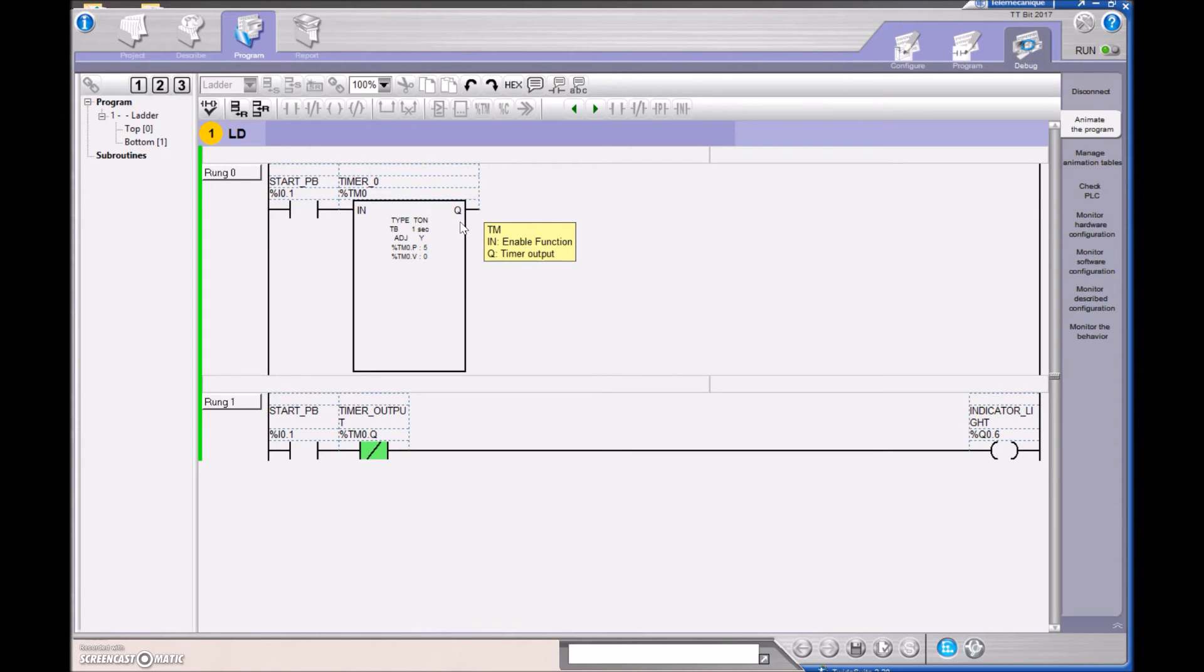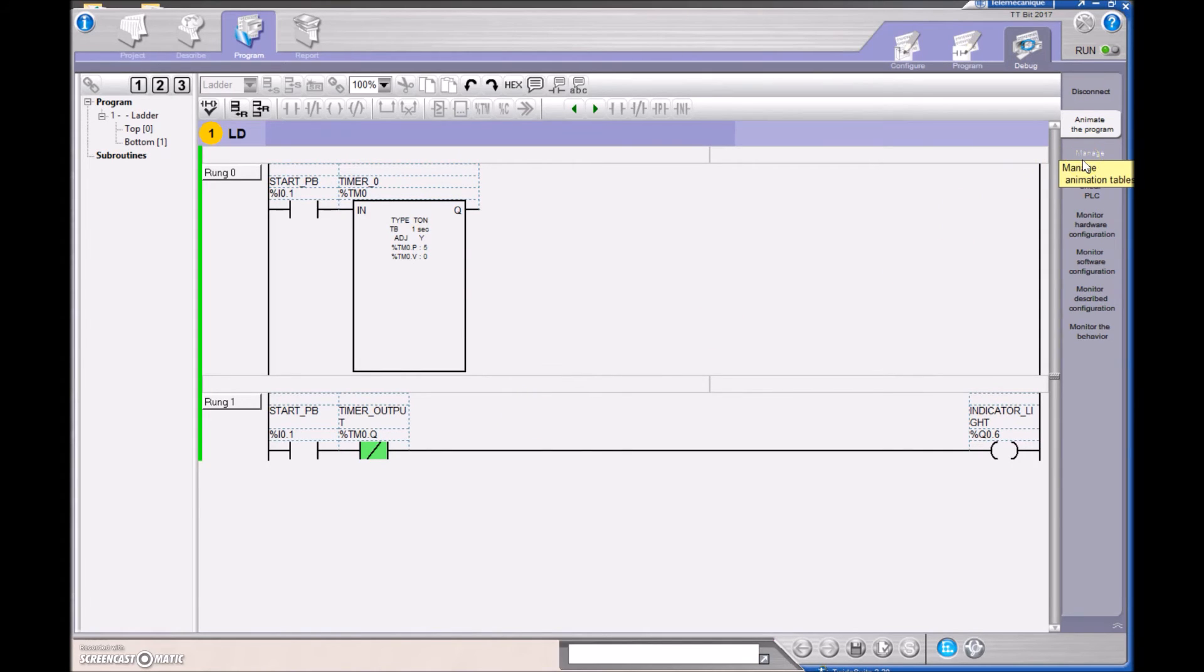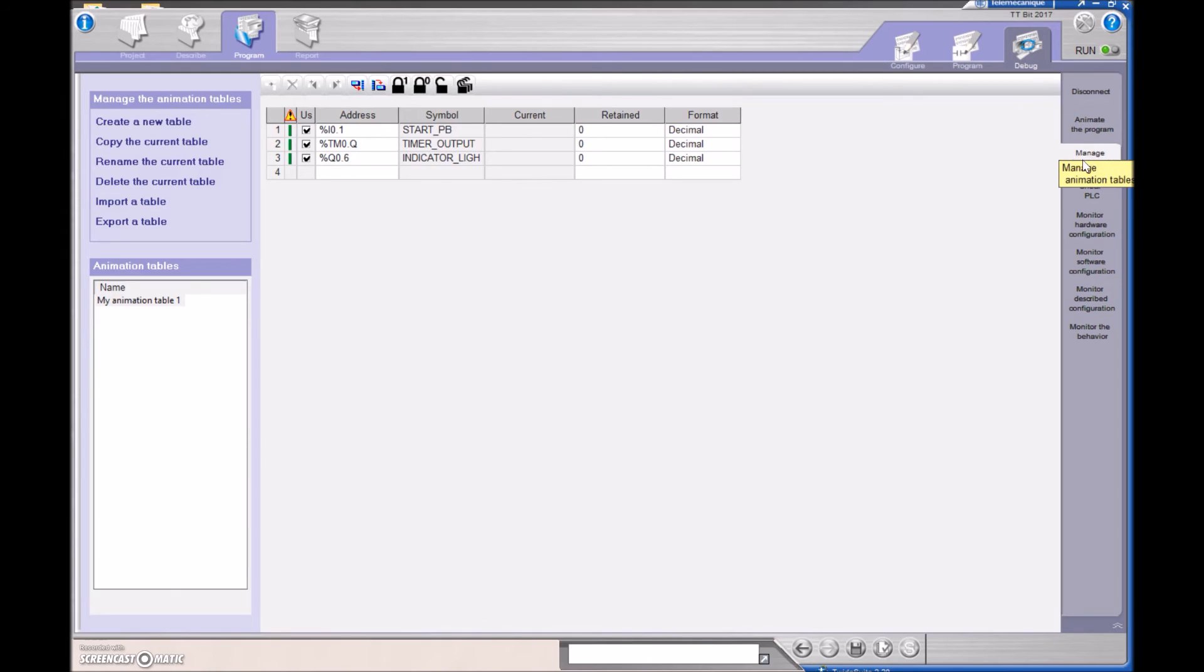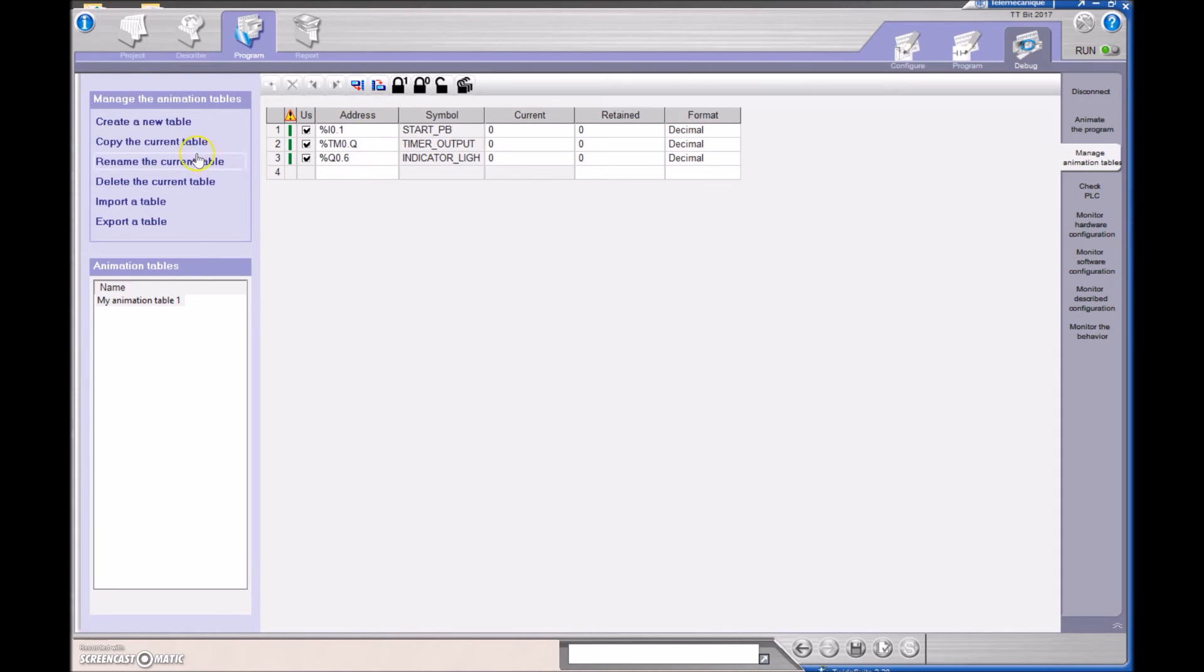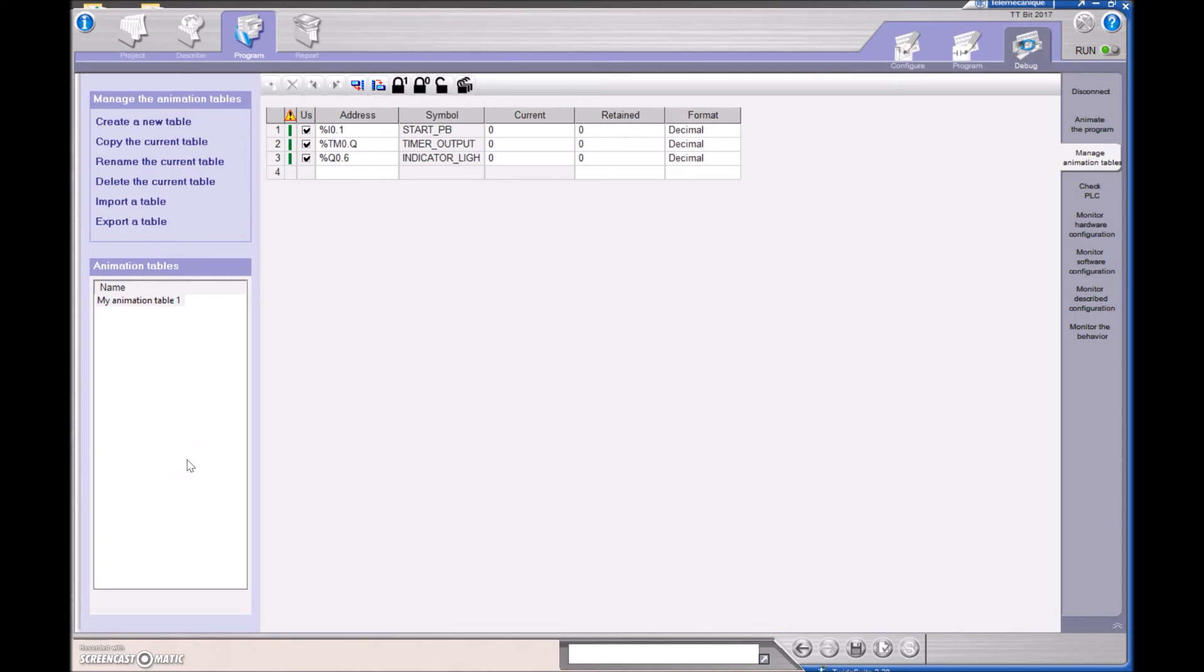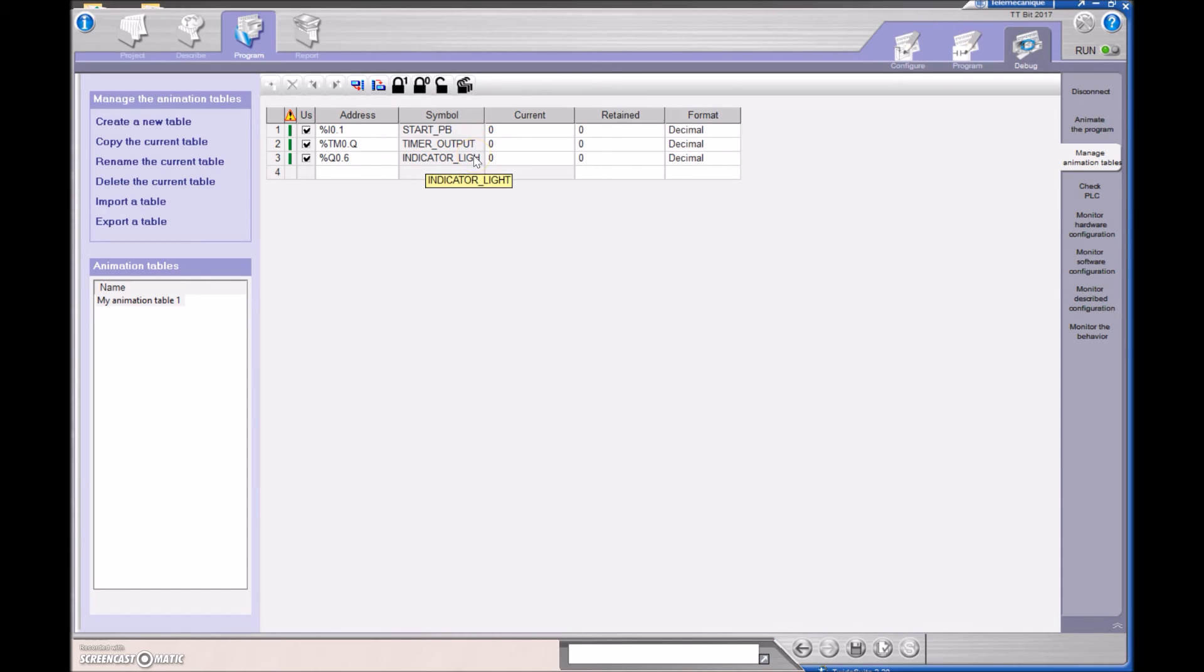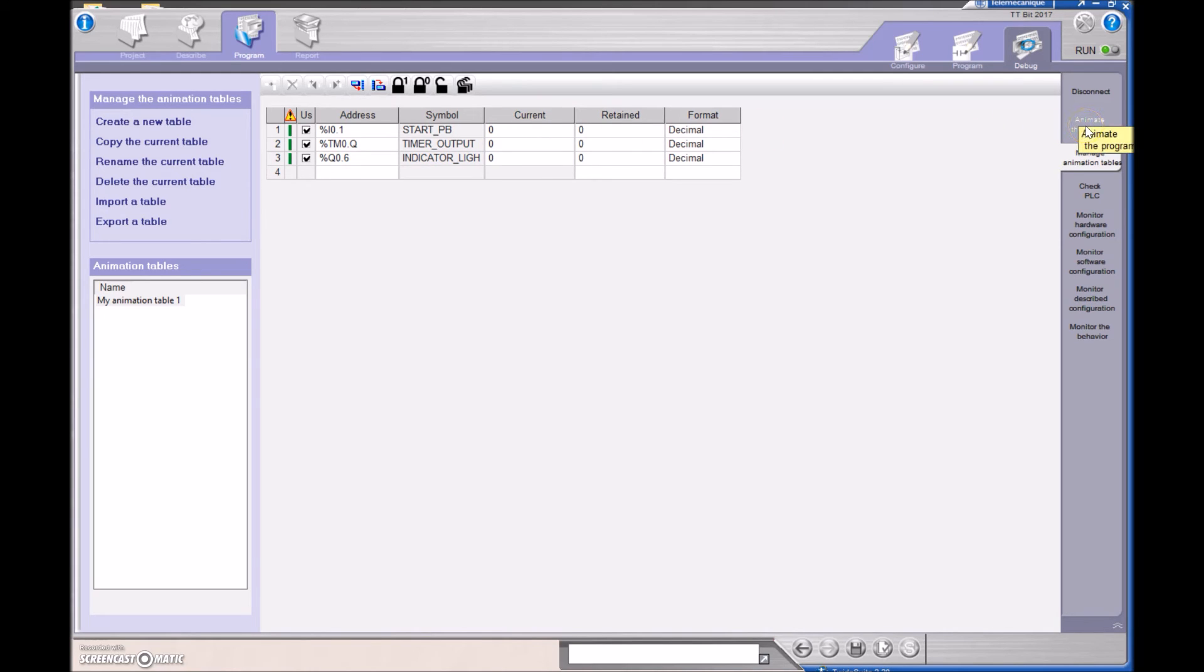The other thing I want to show you in this video was if you want to look at the actual bits, then you can go here to Manage Animation Tables. Now, at this point, I already put in my input, my timer output, and my indicator light, but if this wasn't here, you would just go to create a new table. On the Allen Bradley PLC, they have on the side of your program all of the data tables available. Just double click on them, and you can see the bits in real time. On the Twido Suite, you have to create a table and tell it which bits that you're going to look at. So I want to look at my push button, the timer output, and the indicator light. Once those are in, you're going to have to click here, and then these will set.